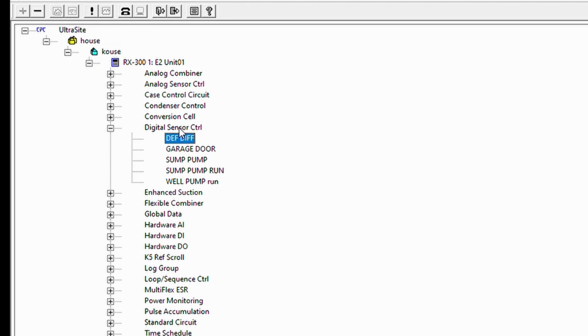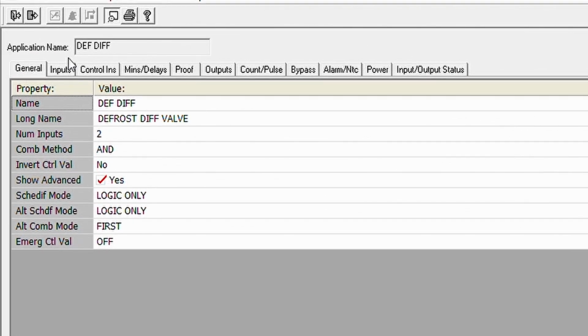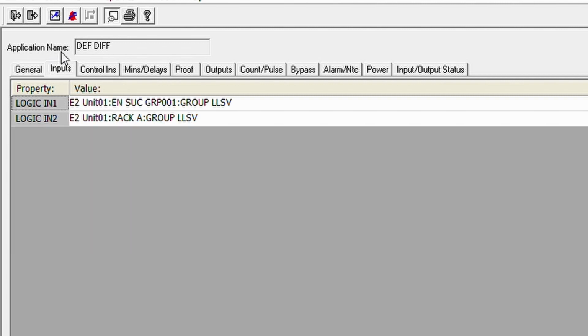So defrost differential valve. Okay, so just like we had here, you have all the drop-down menus. Everything's the same in UltraSite. It's just a lot easier to do it. So you have your logic. You have all your stuff here. So logic in, same thing. You set up logging the same way you do with the analog sensor control. So tie it to the base log, hit apply, hit OK. It's a lot easier to do this on here. On the E2, you have to go to F3 edit and then go to setup logging.